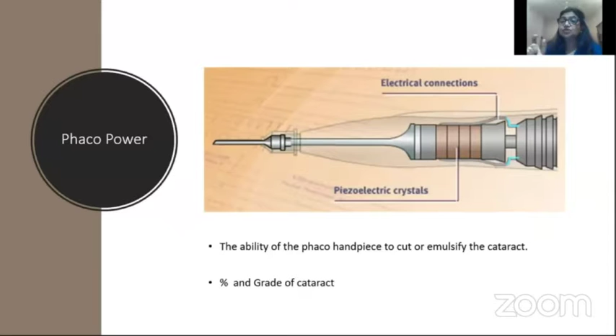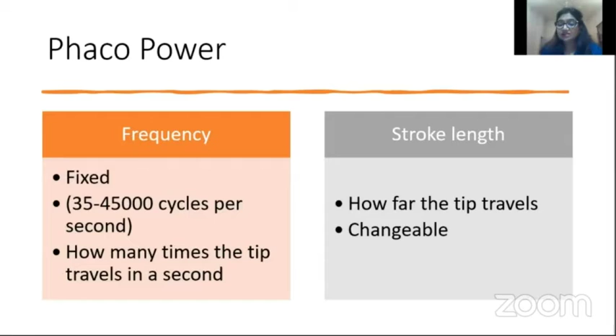It is measured in terms of frequency and the stroke length. Frequency is usually 35 to 45,000 cycles per second, depending on the machine. It is always fixed. You cannot change it. And it basically means how many times the tip travels in a second. The stroke length is how far the tip can travel. So more the stroke length, more will be the phaco power. And this is changeable depending on the grade of cataract. Now the stroke length is how much the tip can move forward.